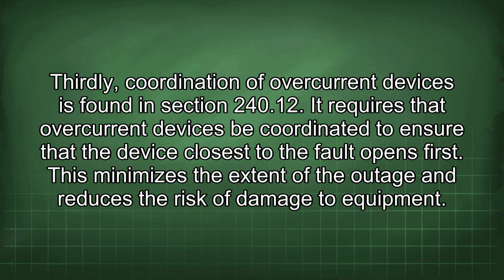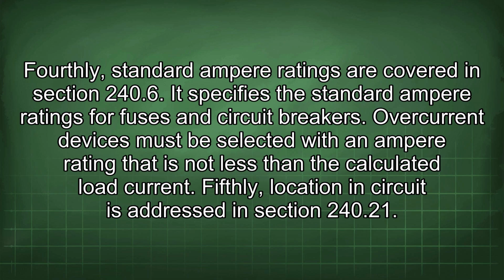Thirdly, coordination of overcurrent devices is found in Section 240.12. It requires that overcurrent devices be coordinated to ensure that the device closest to the fault opens first. This minimizes the extent of the outage and reduces the risk of damage to equipment. Fourthly, standard ampere ratings are covered in Section 240.6. It specifies the standard ampere ratings for fuses and circuit breakers. Overcurrent devices must be selected with an ampere rating that is not less than the calculated load current.